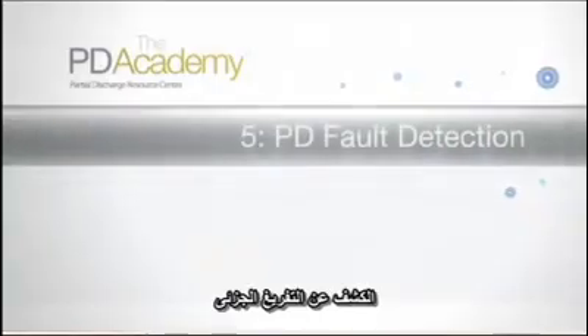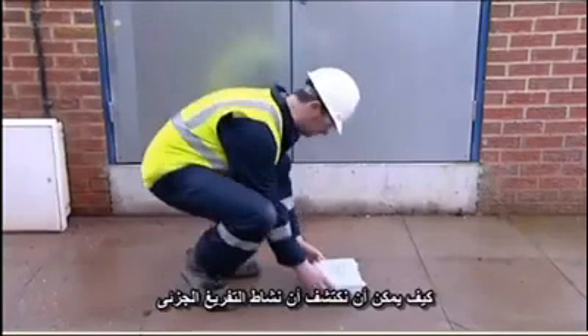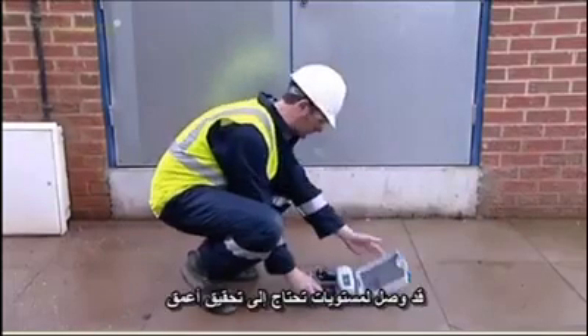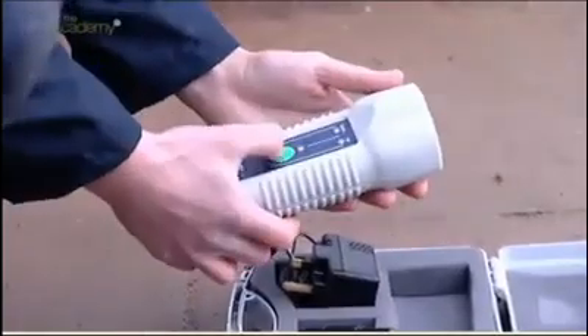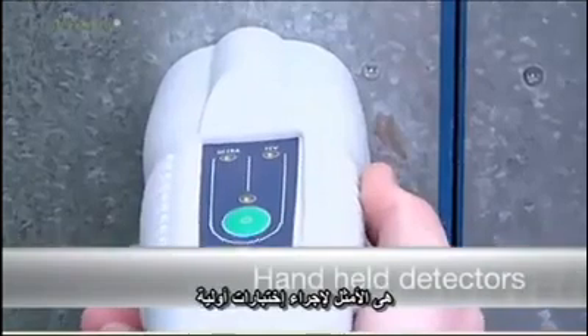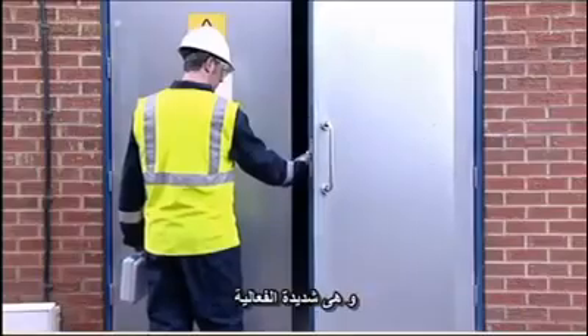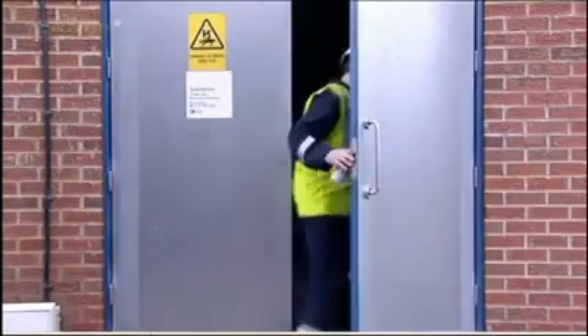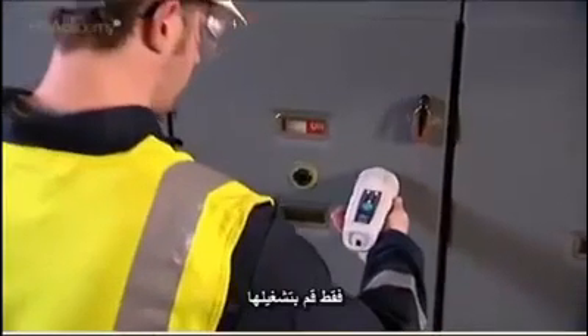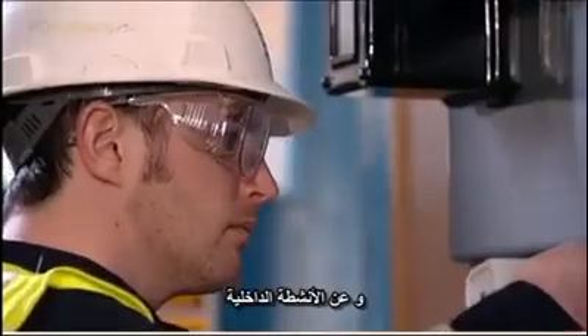PD fault detection. So, how do we find out if PD activity is at a level that needs investigating further? Handheld detectors are ideal for carrying out first-pass surveys. They are easy to use, with little training, and very effective. Just turn on, check for PD activity on the surface of the assets, and for internal activity.